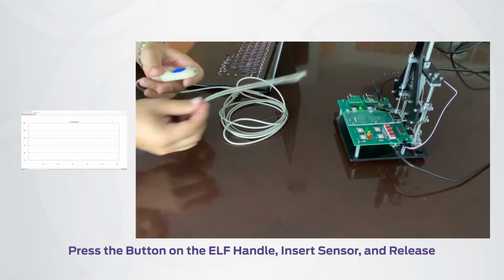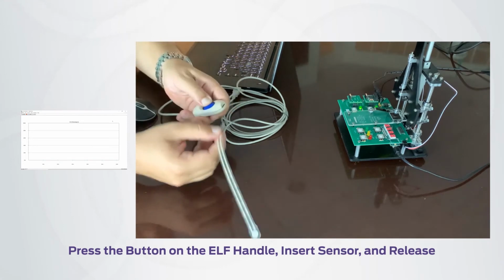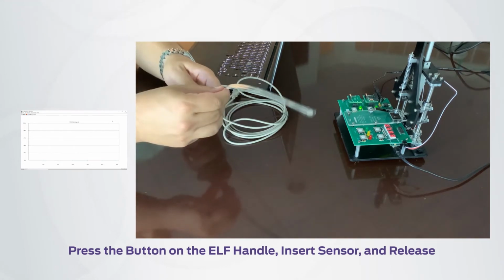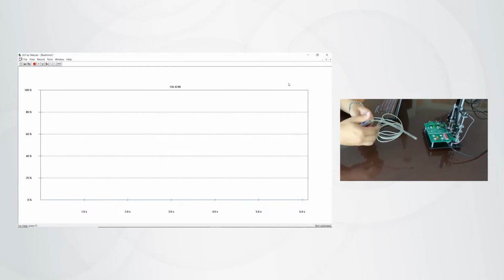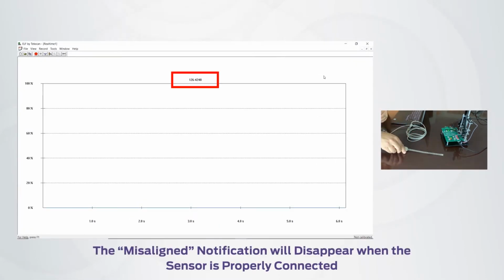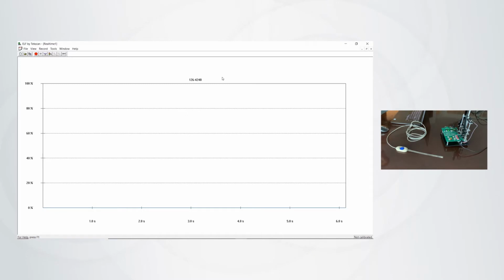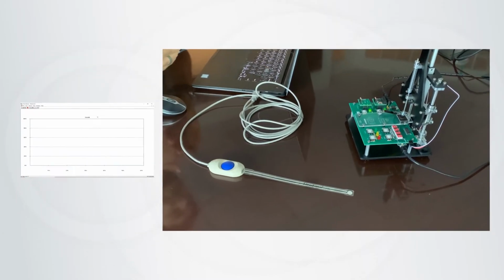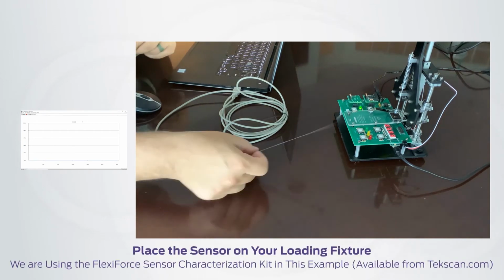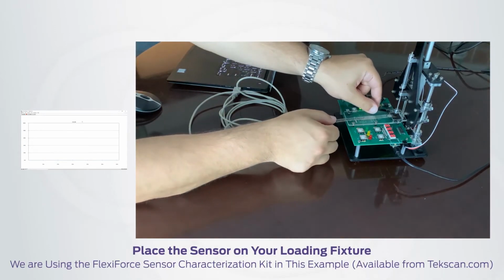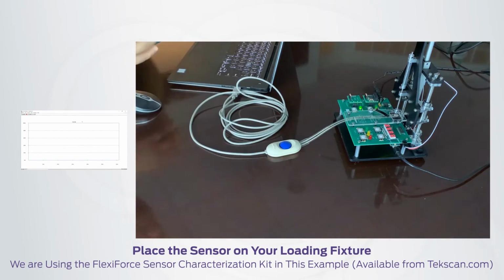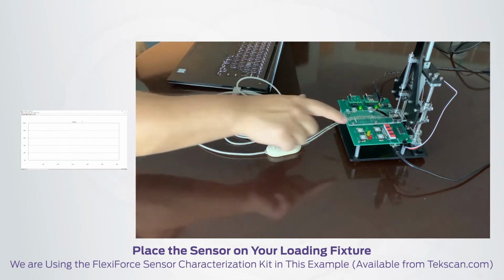To load the sensor into the handle, you simply press down on the blue button of the handle, slide in the sensor, release the blue button, and as you can see, the misaligned text that was near the serial number on the software interface has disappeared, indicating that the sensor is properly loaded in the handle. And now we're ready to load our sensor into our calibration fixture. So the sensor has been loaded in our calibration fixture.